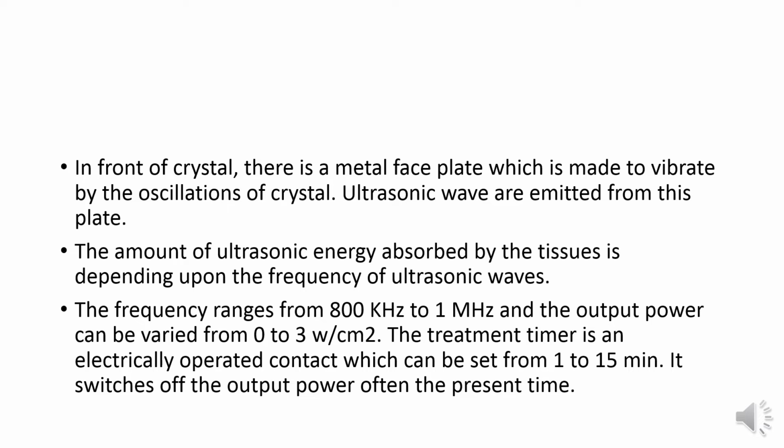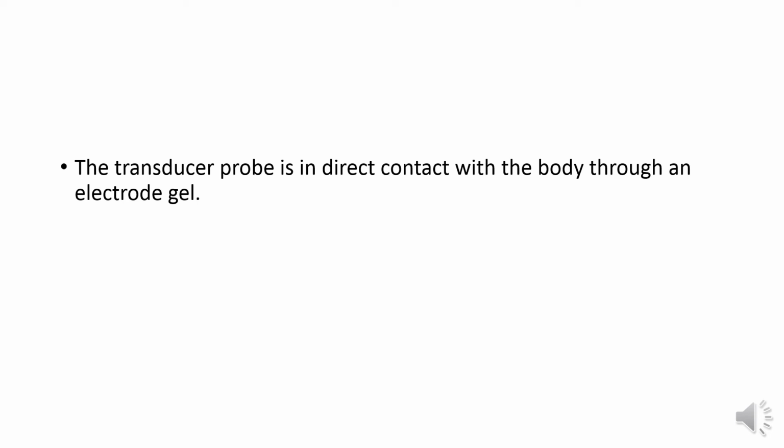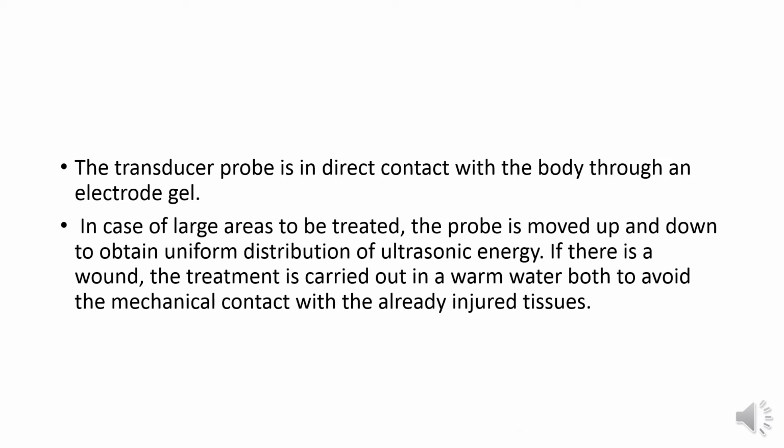In the treatment we have a timer. This is electrically operated and can be set from 1 to 15 minutes. Then it switches off the output power after the preset time, so that we save the power. The transducer probe is in direct contact with the body through an electrode gel. For large areas to be treated, the probe is moved up and down to obtain a uniform distribution of ultrasonic energy.